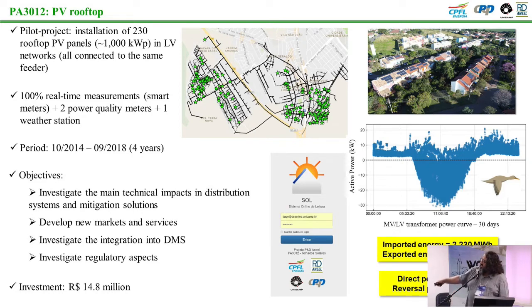You can see the famous duck curve. This is a measurement in our district. We have around 4 or 5 transformers with this kind of PV penetration. The direct peak and the reverse peak is higher than the direct peak, so we have a very high penetration of PV in this low voltage system. You can even see over 1 month the energy flows more from the low voltage to the middle voltage side. It's a very high PV penetration in the field.